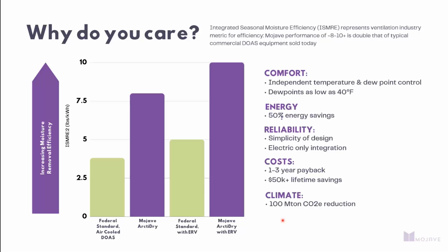From a payback and ROI perspective, we're positioning this to be a small premium over hot gas reheat style products, but that ROI on first cost should fall well within that 1 to 3 year payback, depending on what location you are geographically. Additionally, this does fall into the decarbonization portfolio. We're offsetting about 33% of our refrigerant volume in our units with liquid desiccant. So only 67% of the refrigerant of a conventional hot gas reheat system is in our product.